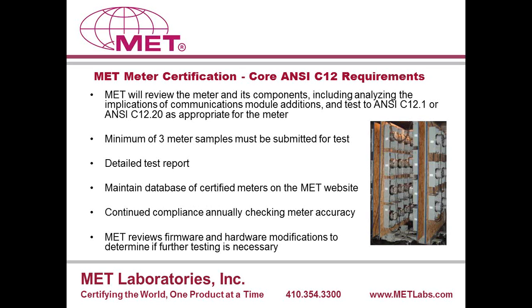So getting into a bit more of the detail of the ANSI C12 requirements for our meter certification program. How it starts out, of course, is folks will contact us. We've got a product. They'll submit a request for quotation, and the people here at MET will take a look at the meter. What is the configuration? Is it a family of product? Does it have wireless modules installed? All the details about the product itself. A quotation will be submitted, a test plan will be developed, and we'll get into a test program. Minimum sample of 3 meters. If you have a family of products, for example, you may have different current ratings.